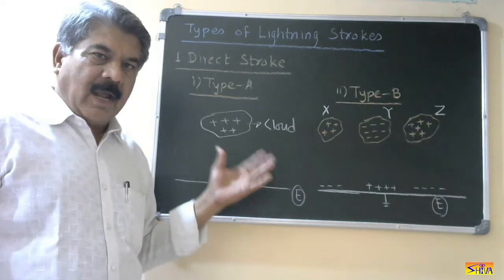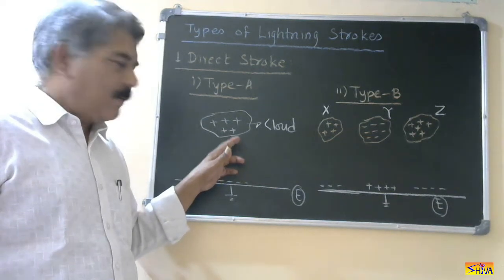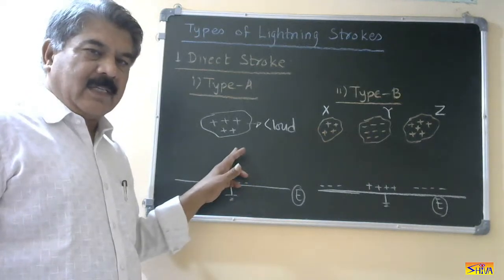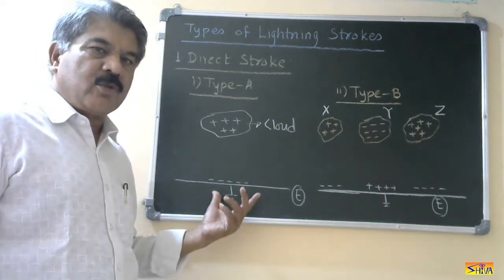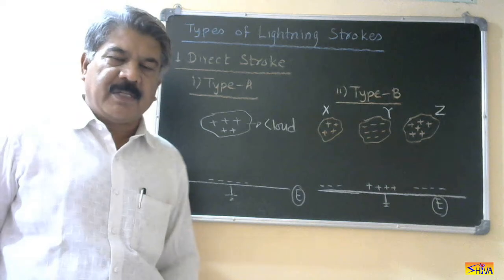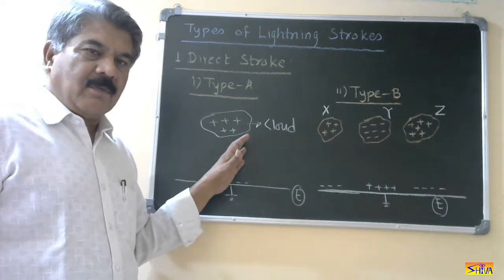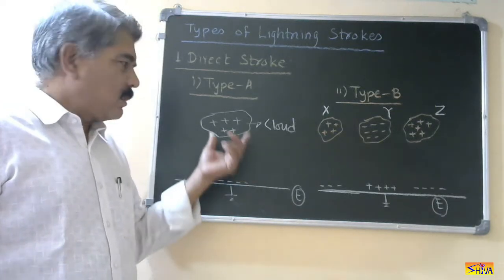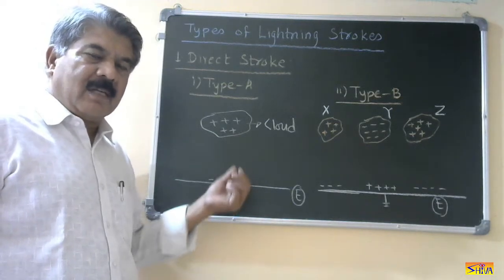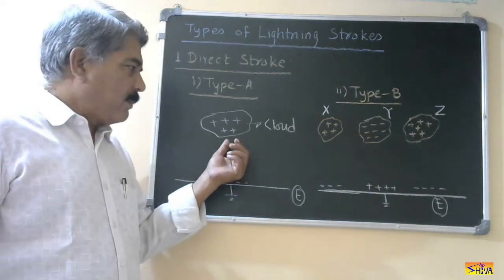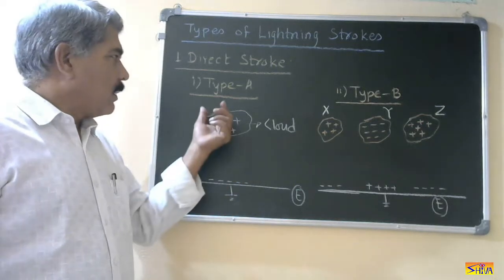The lightning mechanism will be the same. When sufficient charges are present, a channel is established — that is the pilot leader or pilot channel. When it approaches the ground, a positive streamer channel is established and finally there is discharge of the cloud on the ground, or on the topmost object on the ground, which can be a transmission line or transmission line tower. This type of discharge always strikes the topmost object below the cloud, and that is called a Type A stroke.